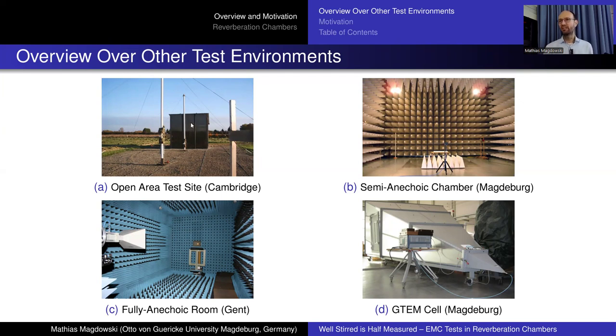And today you have so many ambient fields on the outside that you measure lots of cell phone networks, radio stations, and so on. So you need to somehow shield yourself from the environment. The topic of shielding was just the topic in a lecture of Professor Schuster, who invited me here to Hamburg. So the idea is that you shield yourself from the environment. You take metal walls, a metal floor, metal ceiling, metal doors, and metal works for the electromagnetic waves like a mirror. So all waves from the cell phone networks and radio stations that come from the outside are mirrored back, which is nice.